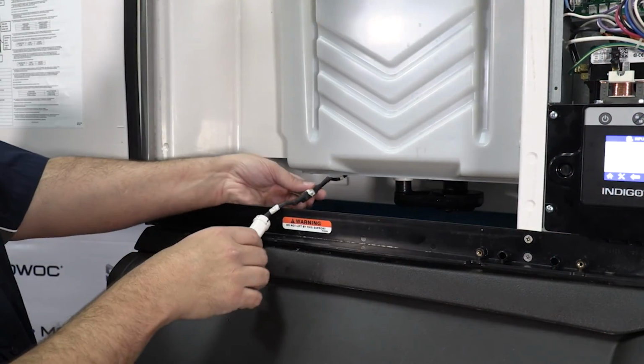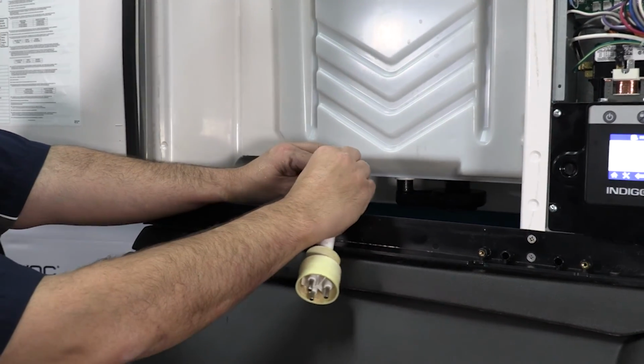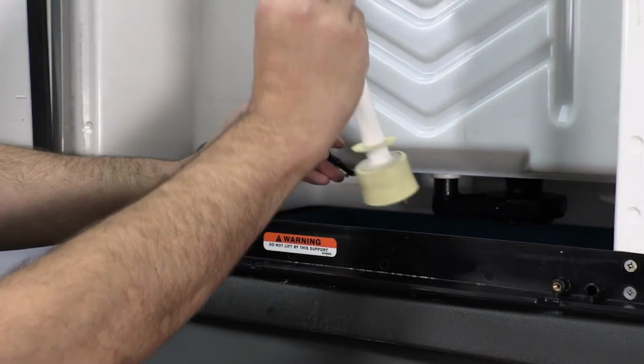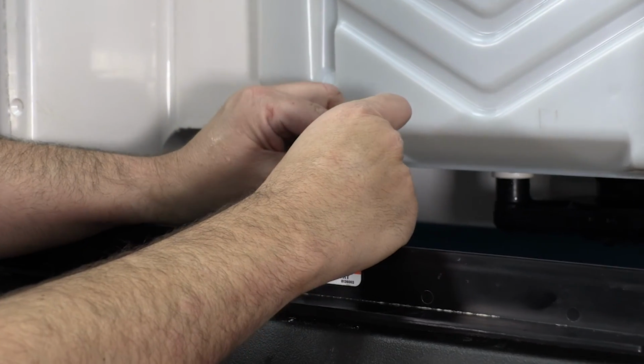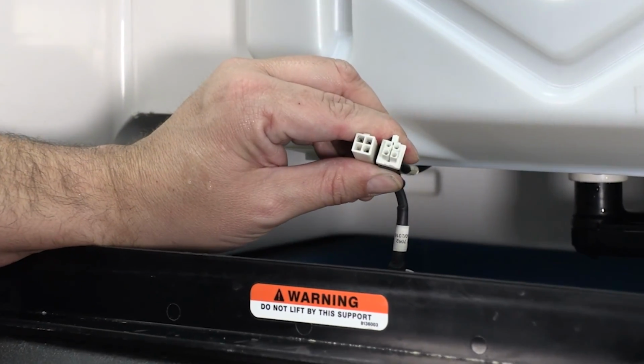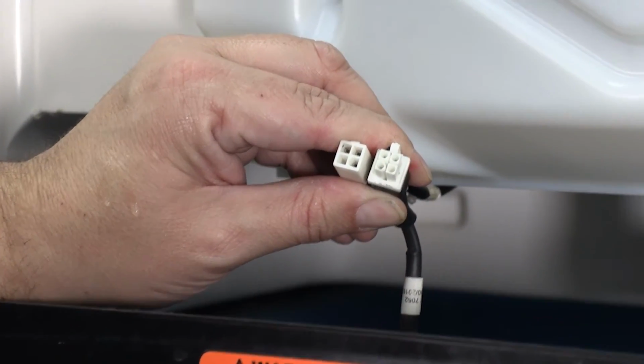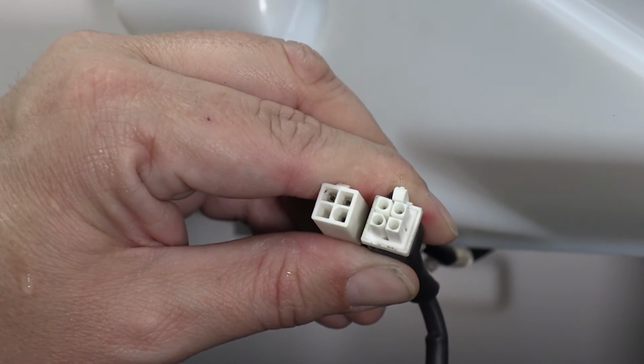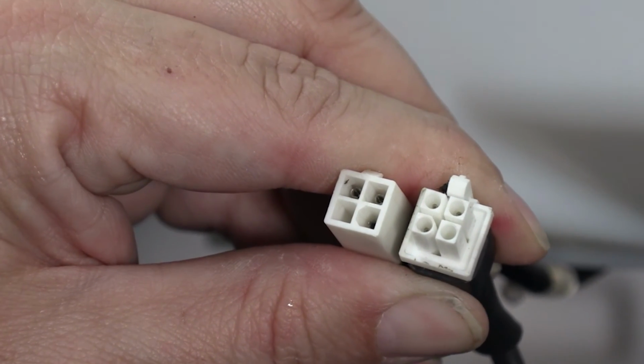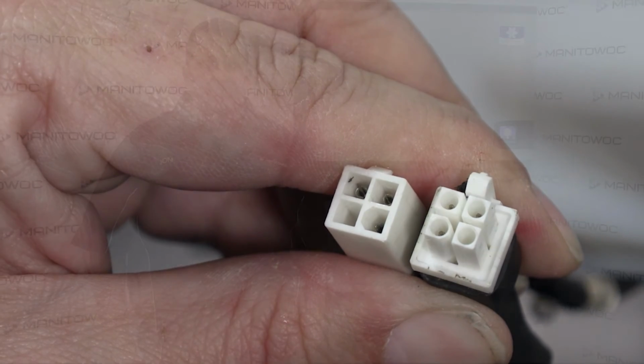Intermittent water faults can be contributed to the connectors on the wiring harness becoming loose or misaligned. On some older versions of firmware, if the control board sees the high probe satisfy before the low probe, the ice machine is programmed to start a harvest cycle.